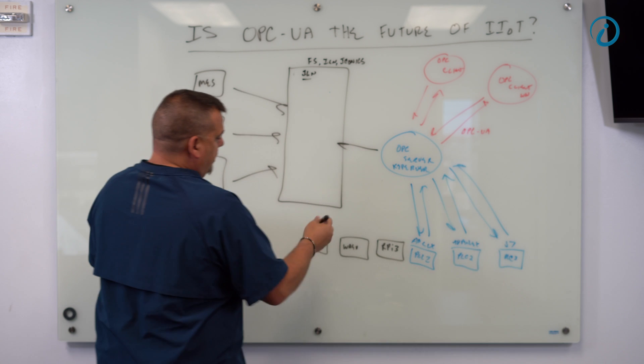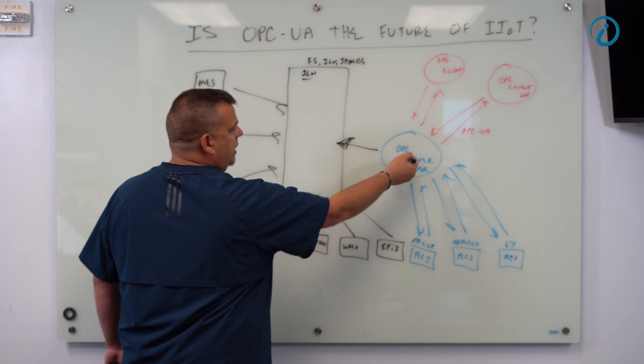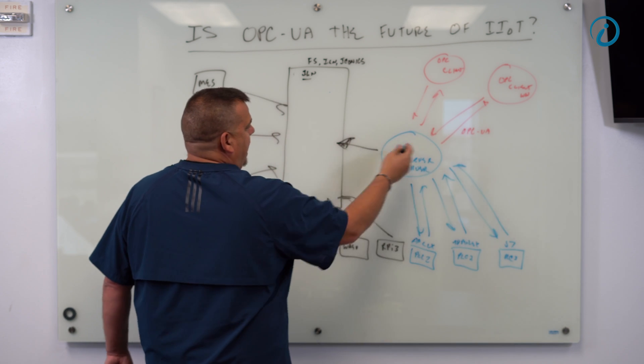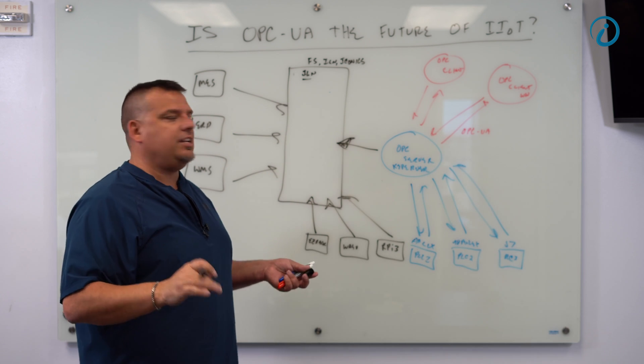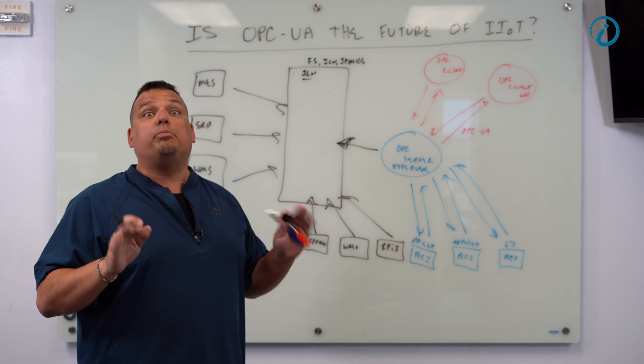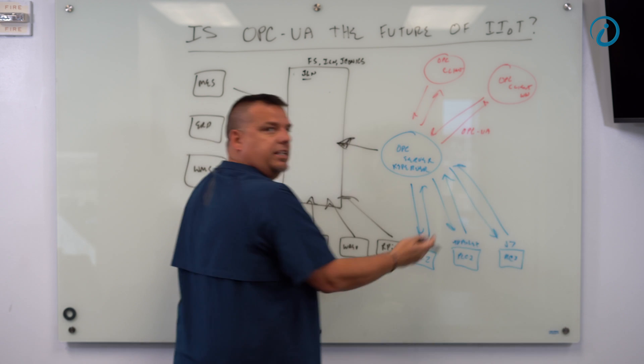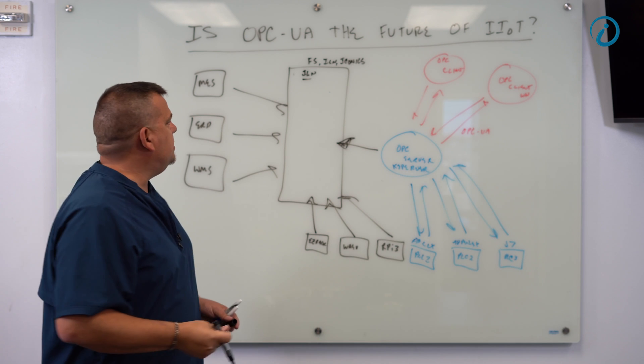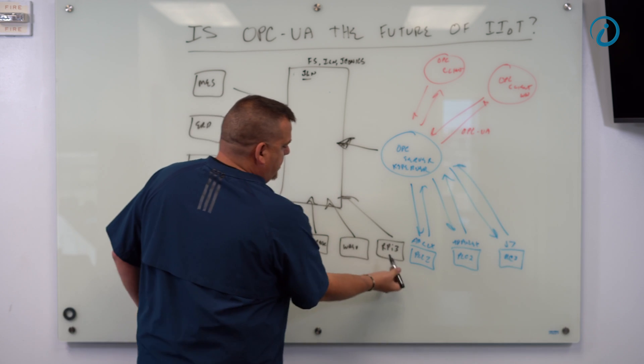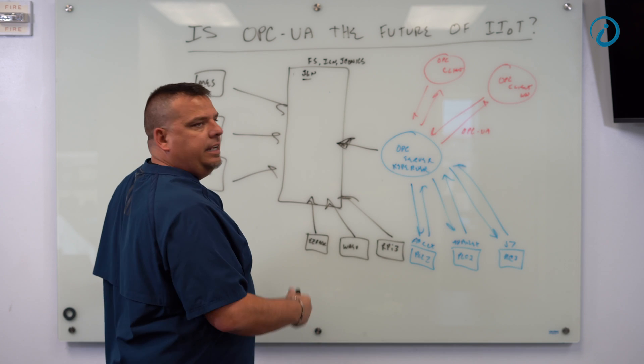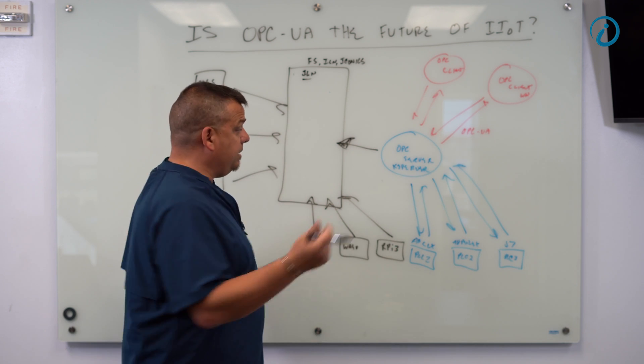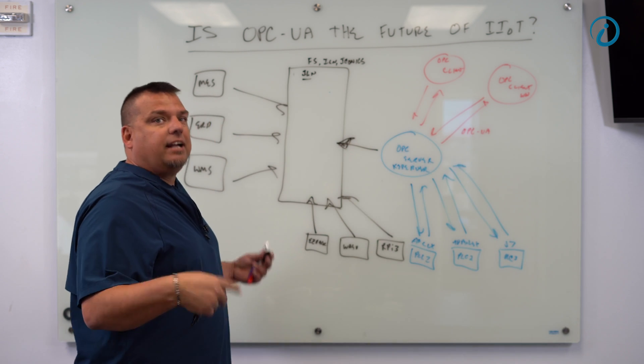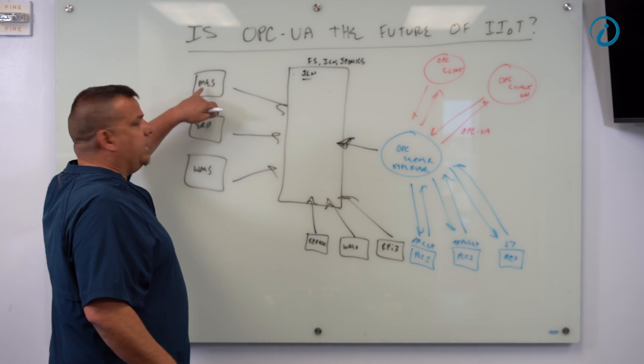When we generally do a project like this, we will connect here with Kepware, use the IoT Gateway, which talks MQTT. We use the IoT Gateway and the OPC server that they have in their existing architecture becomes the report by exception node. This all becomes a big node in the system. And we'll report by exception from the OPC server using Kepware's IoT Gateway. And then our Raspberry Pi, our WAGO, our Easy Rack PLCs, everything else, Siemens Step Seven, the 1200s now support MQTT. They all now publish into the namespace automatically report by exception. And then we can do the same thing.